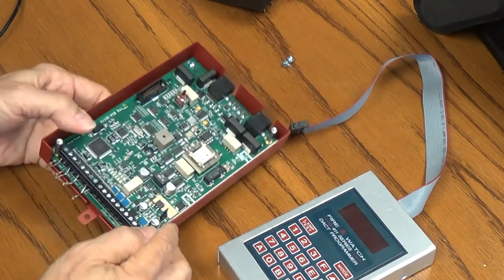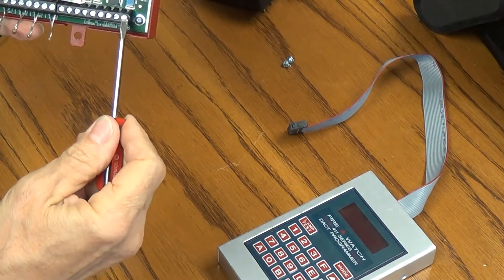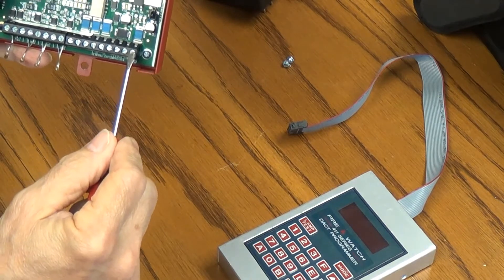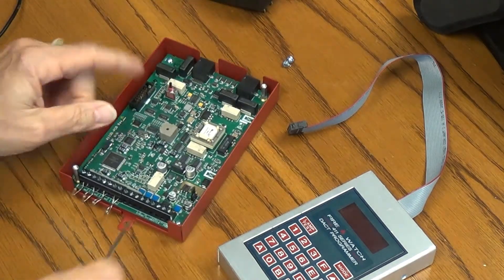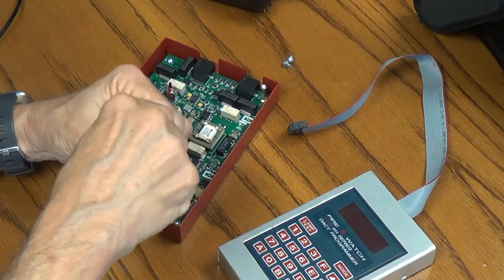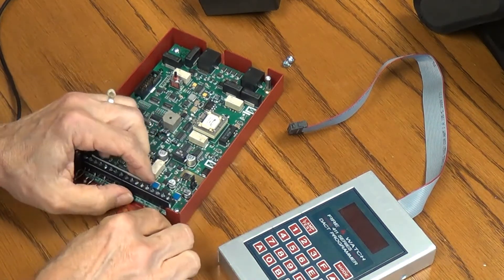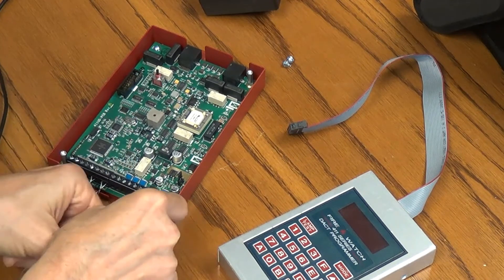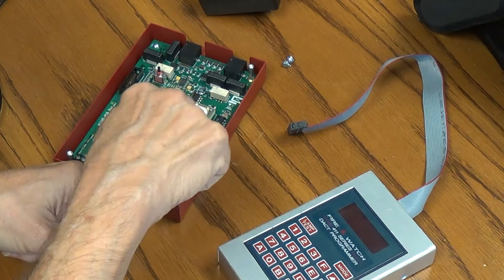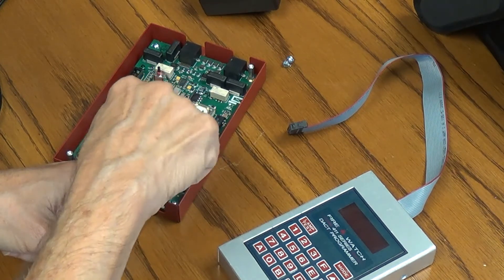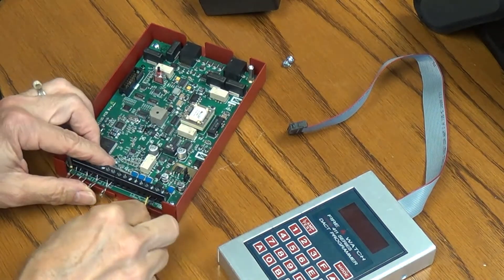Here you can see there are connectors. We're going to be using these to power it up, and we're going to use this one to connect to the FireWatch. Next thing we do is connect the power to these terminals. Now, the last one here is not the one you want to use. That one would be connected to chassis ground. It's going to be the second and third from the right. Second being ground, third being the positive voltage. I'm going to turn these counterclockwise to release the connectors, then put the wires in and turn the screws clockwise to tighten them up. Nice and tight.